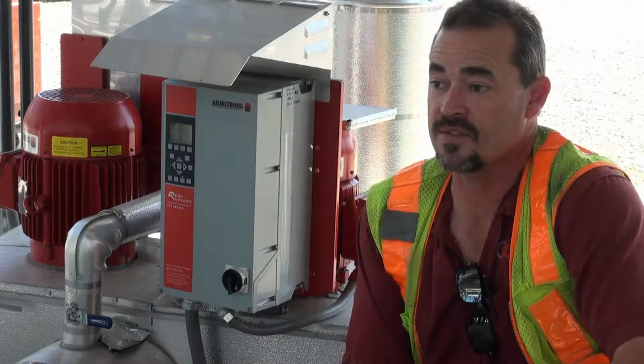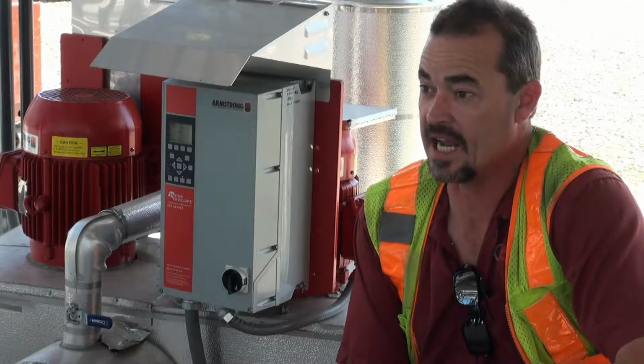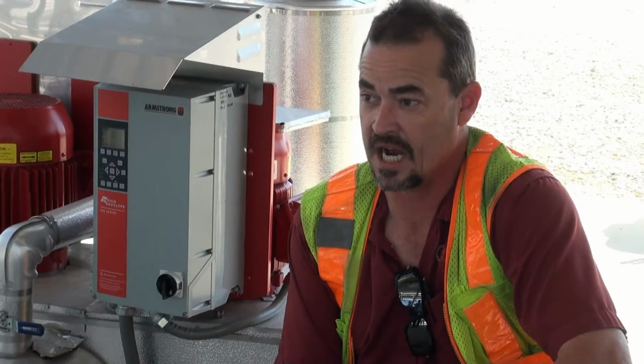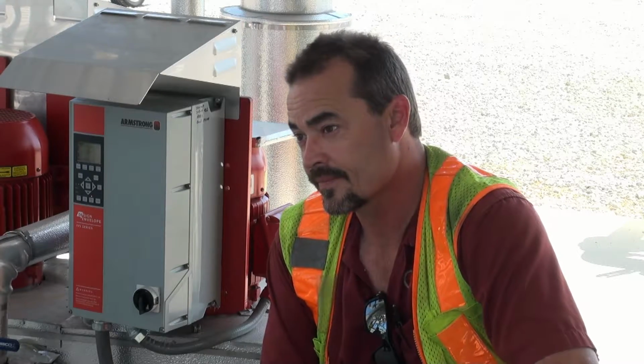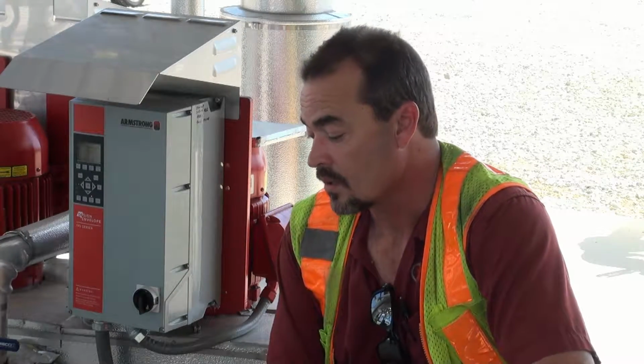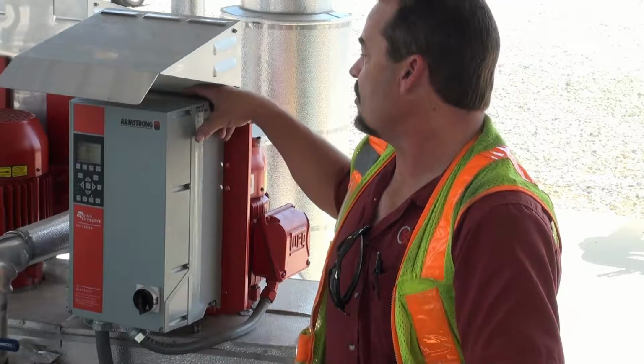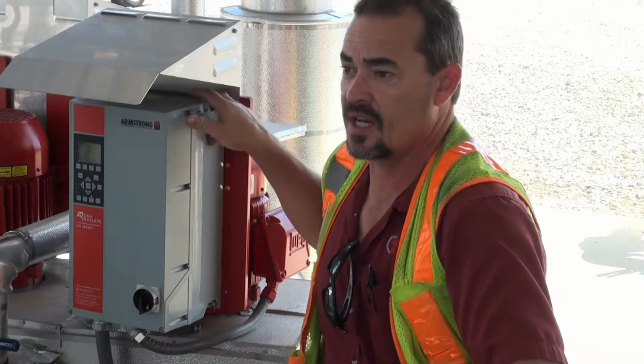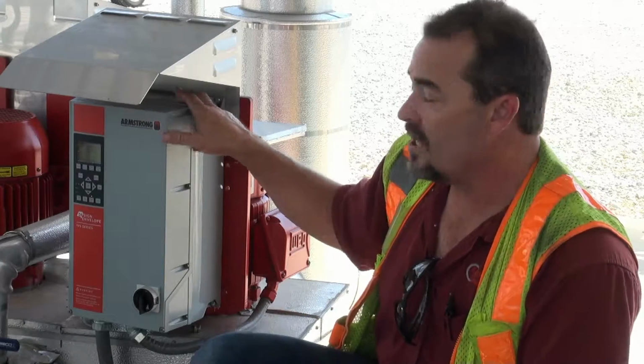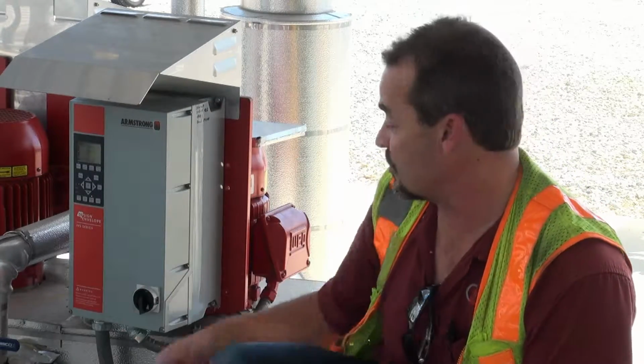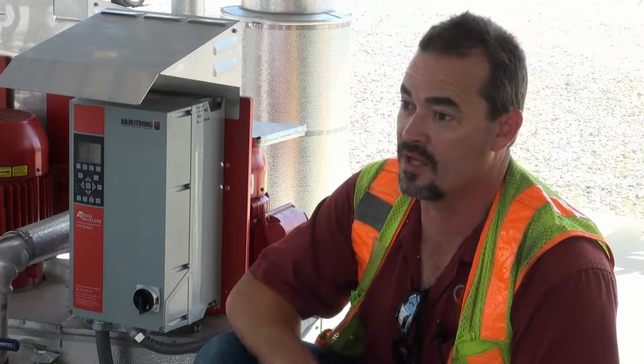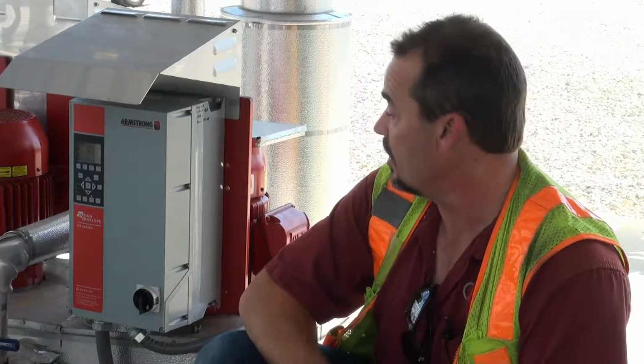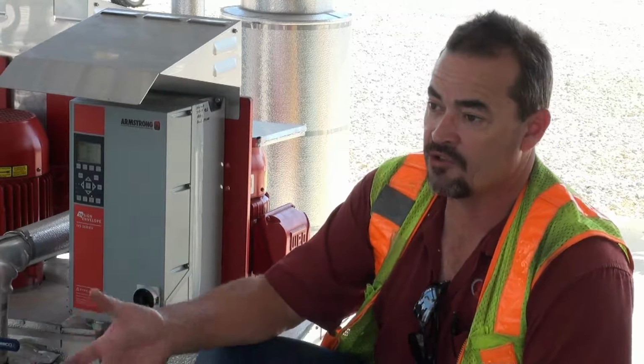One thing with the drives, it really should be checked and cleaned annually. All the connections should be tightened, and so on and so forth. You see this stuff floating around here. Are the fins inside the drive big enough to allow that to flow through the fan? They're pretty good size, you can look up on the top and see the fins coming through. That's not too bad, but nevertheless, some bird feathers and so on, and pretty soon it's clogged up. So yeah, it should definitely be an annual thing.